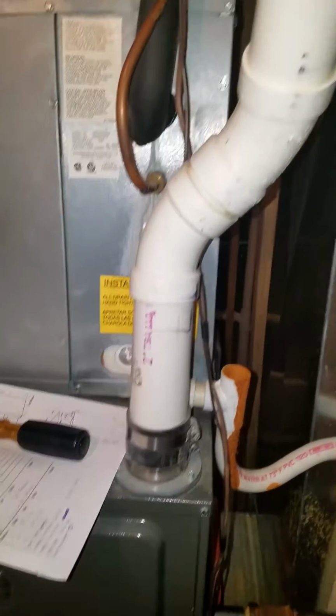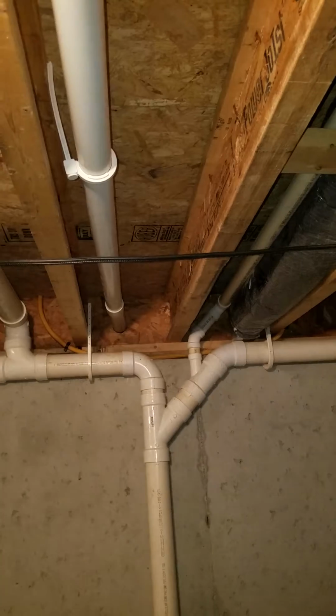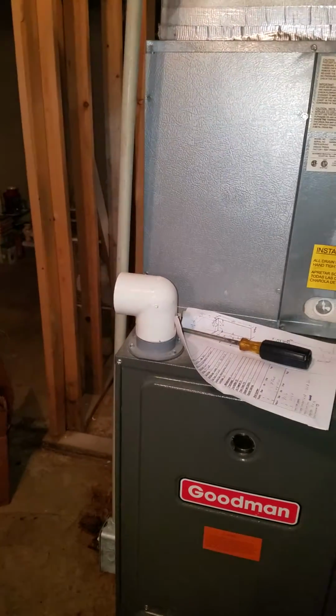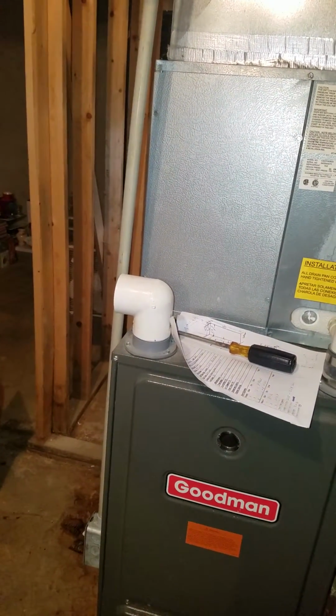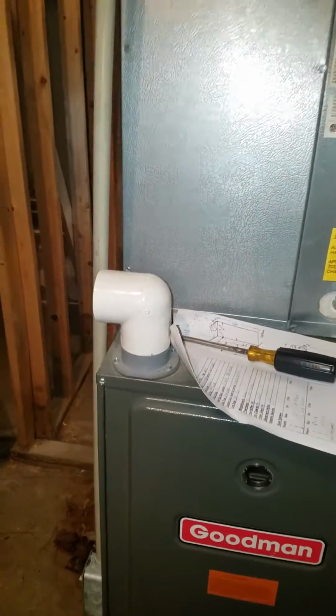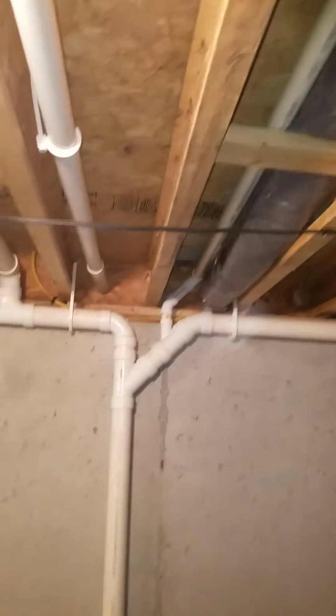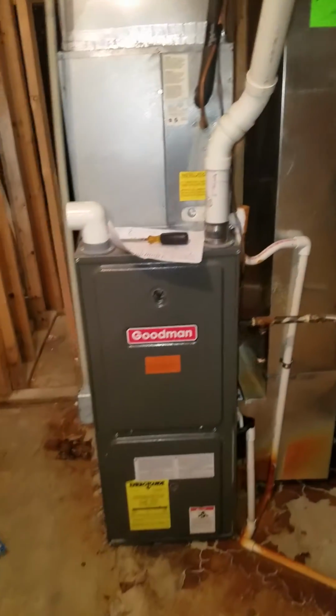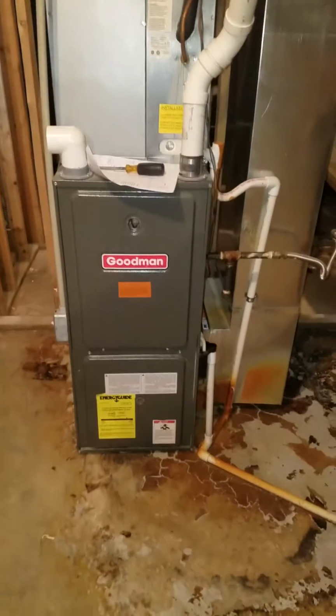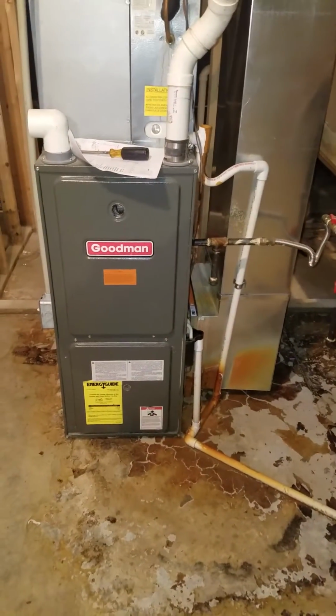So you have a 2-inch one vented PVC that goes right out the side of the home right there. And you can follow that, but only one. And we're free drawing from this. One of the things that needs to be changed here is this needs to be a double pipe system, and you need to run another pipe out the side so we can get some fresh air draw instead of drawing from the basement, and that would help the economy of the furnace quite a bit.